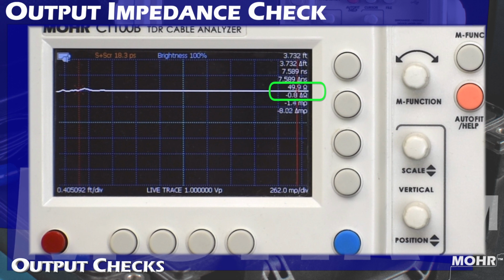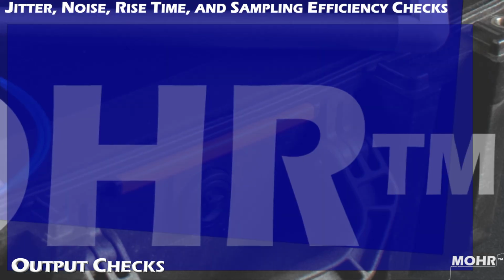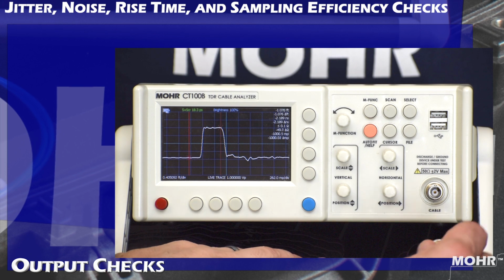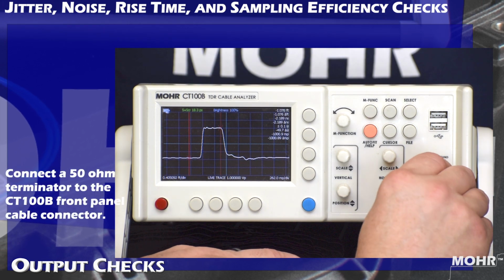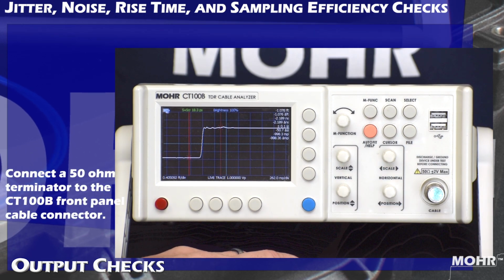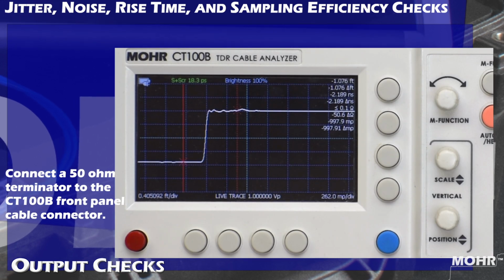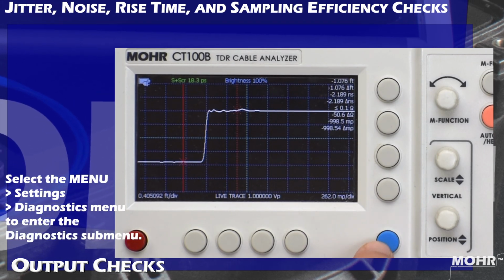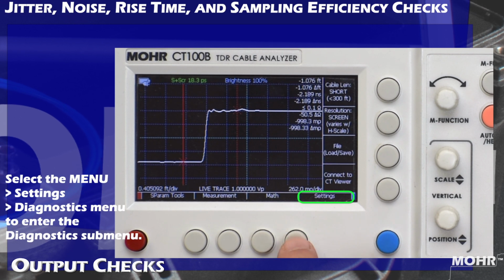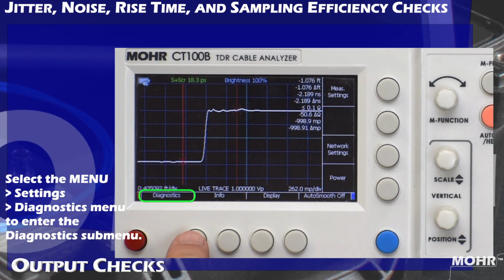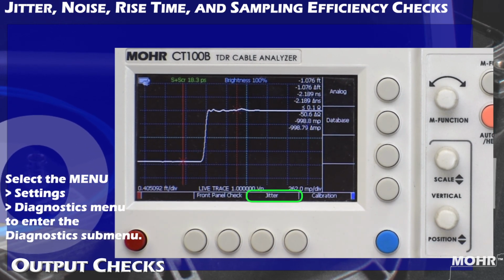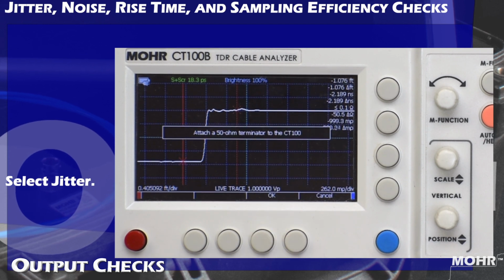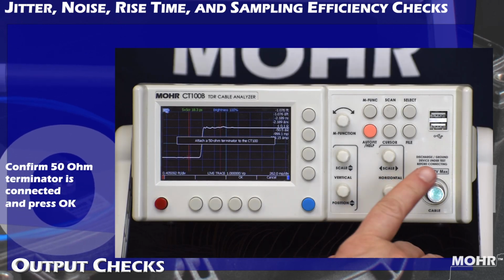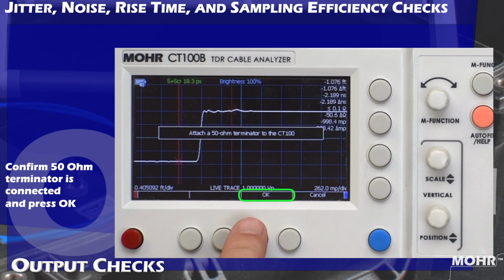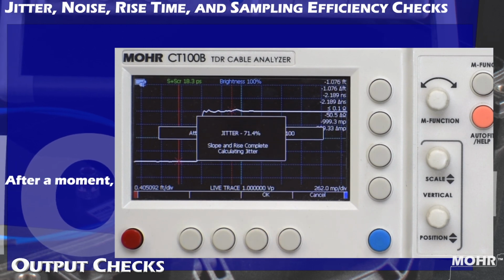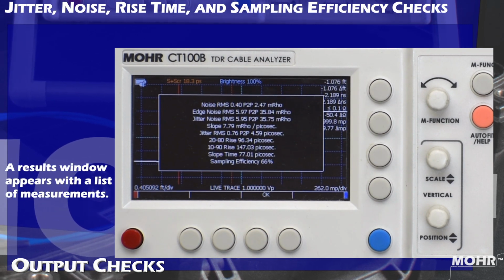For jitter, noise, and rise time sampling efficiency checks, we're going to connect a 50 ohm terminator to the CT100B's front panel cable connector. Select Menu, Settings, and Diagnostics menu to enter the Diagnostics submenu. Select Jitter. Verify you have the 50 ohm connector attached to the front port and press OK. After a moment, the window appears with a list of measurements.